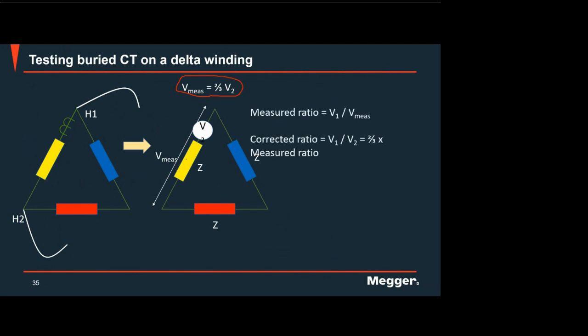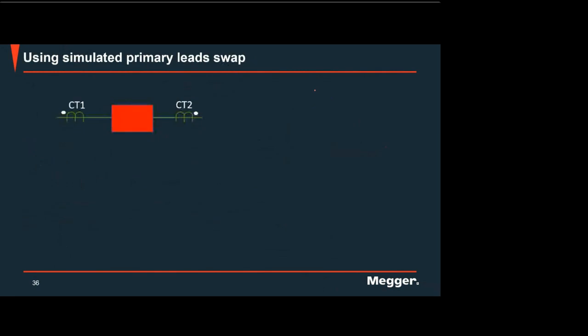So when you measure the ratio, of course, this is the V1 over the V measured, and the corrected ratio is V1 over V2, which is equal to 3/2 of the X, right? Now, the good thing with the MBCT is that you just check this in the setting, buried CT in delta connection, then it will automatically calculate the measured ratio or the corrected ratio. It will automatically display the value, which is corrected. Okay, you don't have to manually compute. That is one of the features of this MBCT.